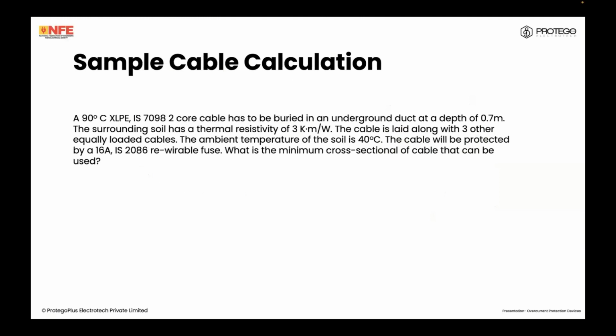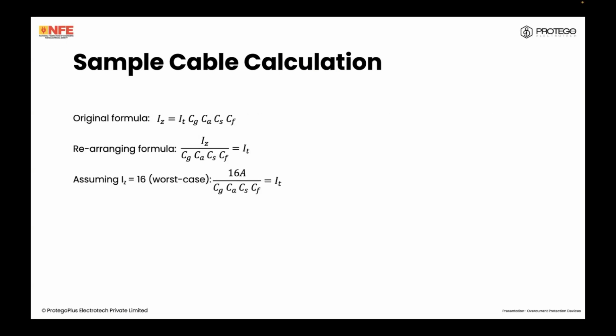A 90-degree XLPE IS 7098 two-core cable has to be buried in an underground duct at a depth of 0.7 meters. The surrounding soil has a thermal resistivity of 3 Kelvin meter per watt. The cable is laid along with 3 other equally loaded cables. The ambient temperature of the soil is 40 degrees Celsius, and the cable will be protected by a 16 ampere IS 2086 rewirable fuse. We need to find out what the minimum cross-sectional area of the cable is that can be used. We'll just rearrange the formula a little bit. We'll assume IZ is equal to 16 amperes. Worst case, 16 divided by Cg, Ca, Cs, Cf will give you the minimum tabulated value required.